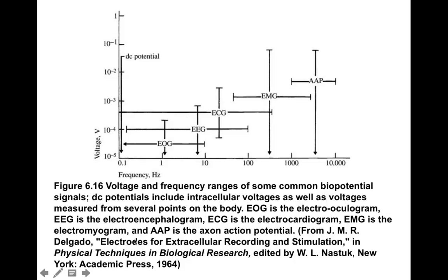There are things you can do in a clinical environment that would be not unlike what you would do in a research lab, where you can provide certain grounding and shielding. You can provide ground planes that give you some isolation from this capacitive coupling.